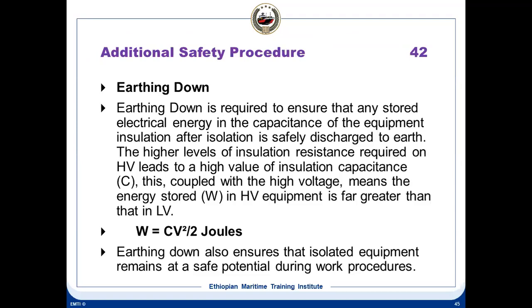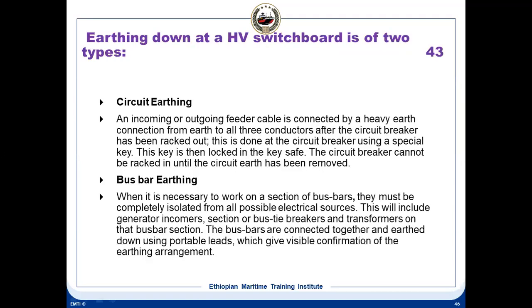It's very important. What is earthing? What are the types of earthing? Earthing done at HV switchboard has 2 types: one is circuit earthing and the other is busbar earthing. Circuit earthing is done on the breaker itself using a key safe. So with a key, you can make a circuit earthing. Busbar earthing is using portable cables.